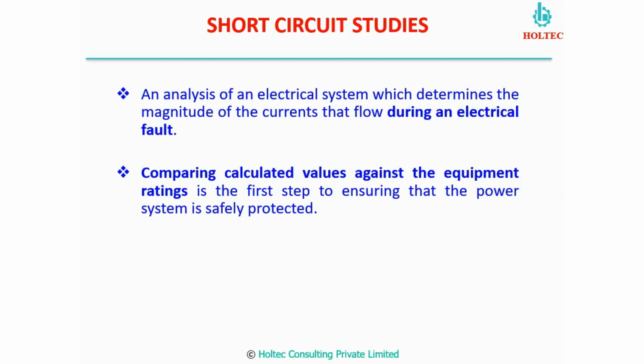When we compare these calculated values against the equipment rating, we can decide whether our equipment is properly rated, or we can design the equipment according to the fault magnitude which we find from the results of the ETAP short circuit studies. This will help not only to decide the equipment rating during the project stage, we can also validate the equipment rating when we do modifications in the system.